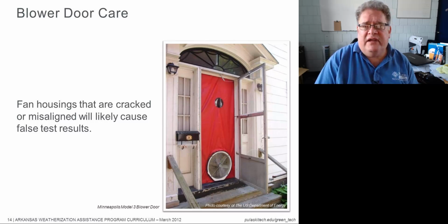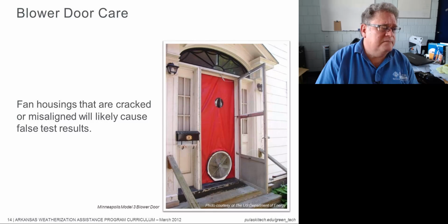If you think you've got a fan that's not good, well, test it against a fan that you know is good. If you've got a fairly new blower door, test that older fan against it. Run a blower door test on the house and come back and change the fans out and run it again. And in the same configuration, you should get numbers that are extremely close to each other. If they're differing too much, send that fan in for replacement or calibration.